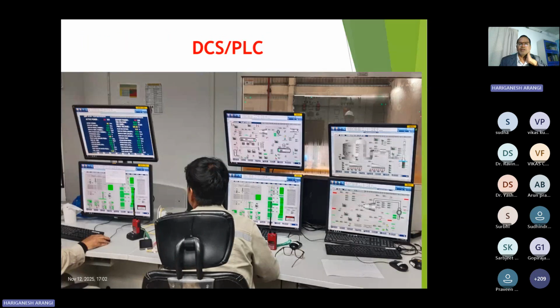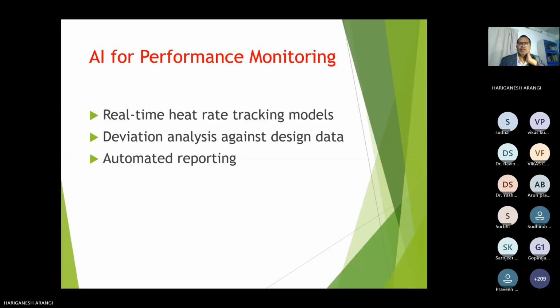The manual analog system is replaced by a proper instrumentation system integrated with the DCS. If you observe the right side, two monitors are showing: the bottom one is the turbine area and the top one is the boiler area. That monitor is for performance monitoring, real-time heat rate tracking models, deviation analysis, design data, and automated reporting systems. If there is any alarm or abnormality in the operation of any equipment, it will give an alarm indication, making a sound, and the operator can take proper action.